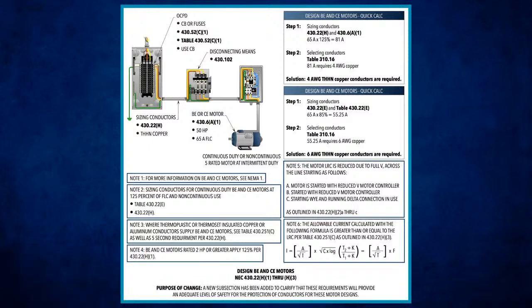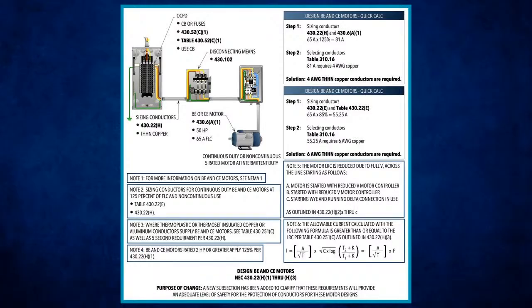Well, if you look, it says the motor compressor, you've got your branch circuit short-circuit and ground-fault protective device shall be capable of carrying the starting current of the motor. Then it says a protective device having a rating or setting not exceeding 175%. So I can't exceed, so that means I've got to drop down. Now, it doesn't matter to me if it's an AC or a motor calculation at this point. The only difference is I can't exceed the calculated value and the percentages can be different.